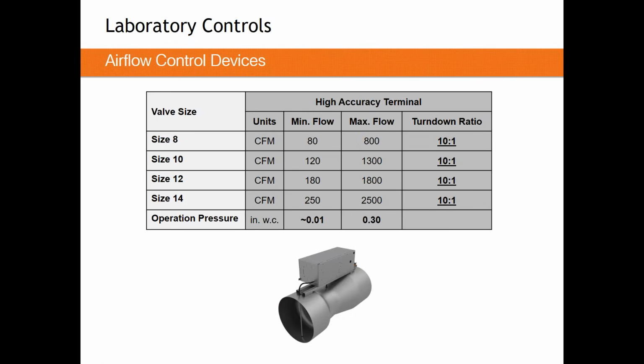Let's look at a high accuracy terminal now. These operate functionally identically. However, they operate at a slightly higher pressure. But the way we read the performance is identical. A size 8 can go from 80 to 800, giving a 10:1 turndown ratio. It can do it with a plus or minus 5% accuracy. But to get 800 CFM out of a size 8 box, it needs 0.3 inches of pressure just to push that airflow through.